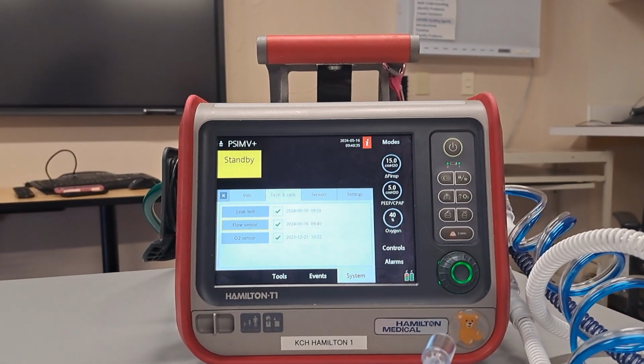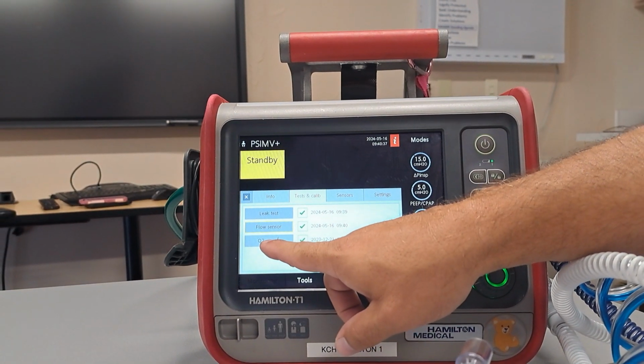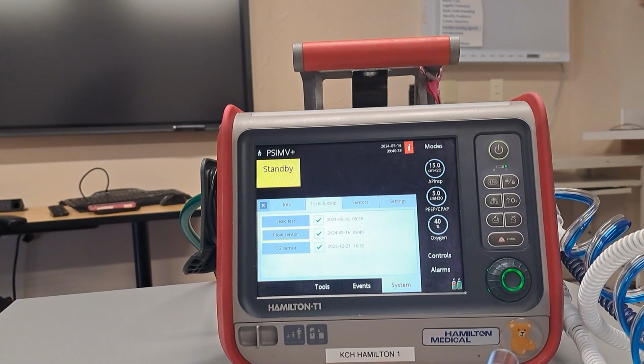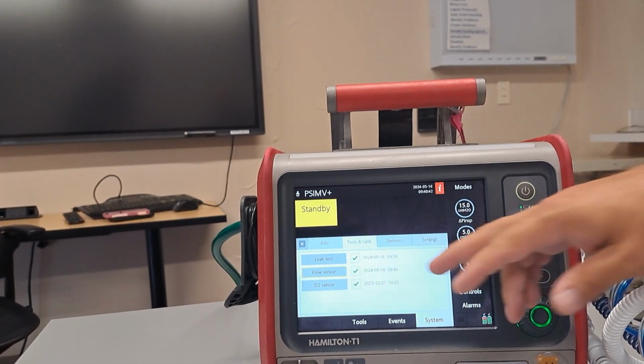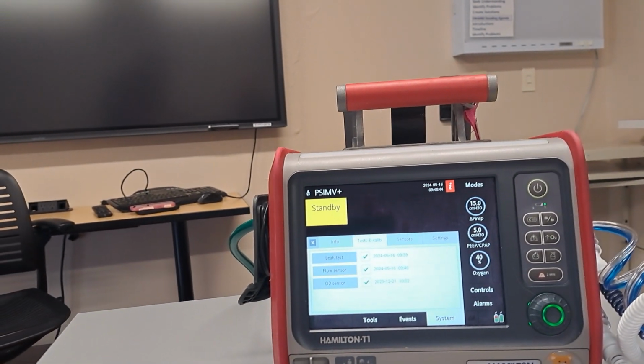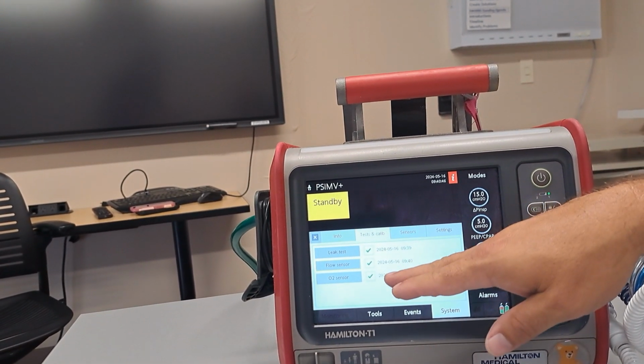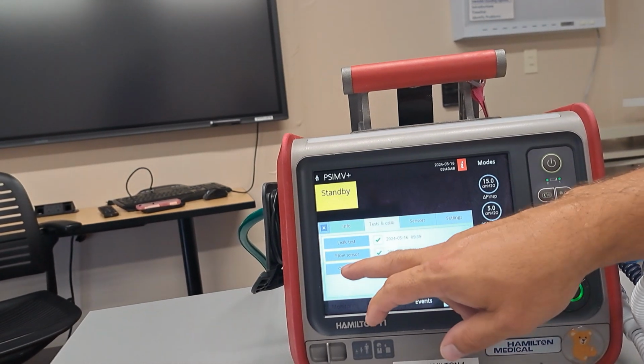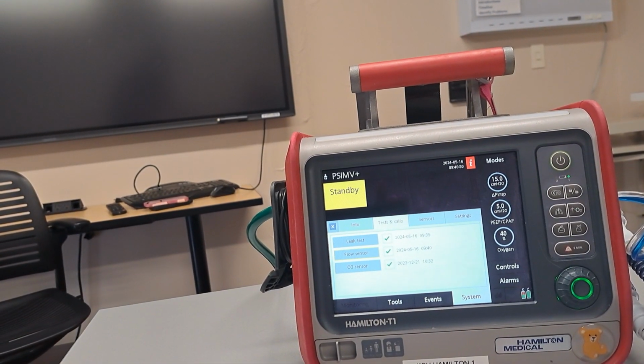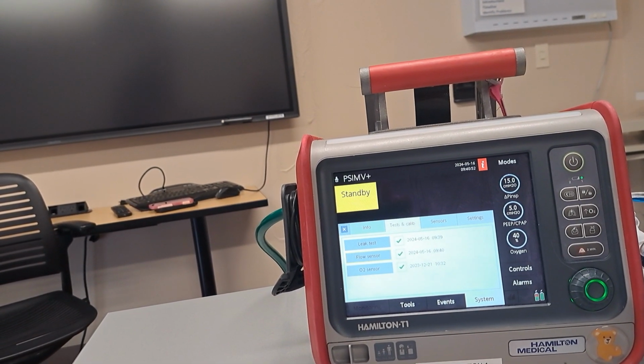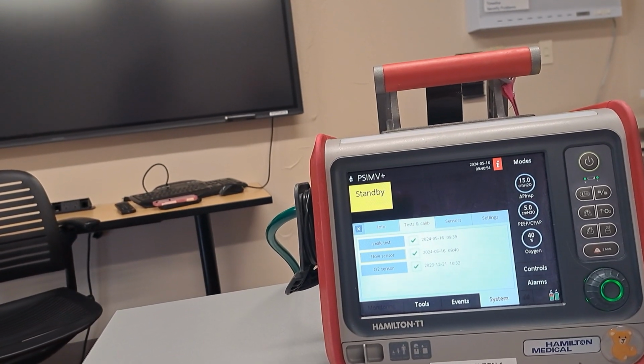So then the next thing that we would normally do is the O2 sensor test. That doesn't have to be done every day, but that's something you will want to have done at least once a week. And because that takes a little time to do, I'm not going to do that, but all you have to do is press O2 sensor test, and there's no flipping of anything. It automatically does the O2 sensor test, okay? And that is how you set up the circuit and do the pre-use check on the T1 ventilator using the neonatal circuit.